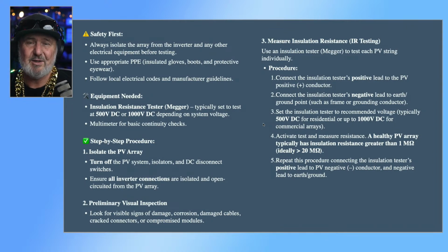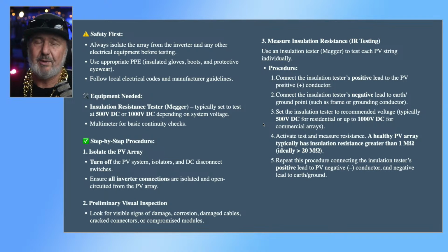Is there anything being damaged? Have we had a hailstorm and there's broken panels? Is there signs of internal failure within the module? So a module might have signs of burning or brown spots. And look at the plug and sockets.